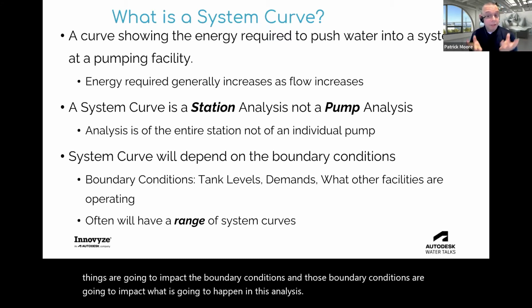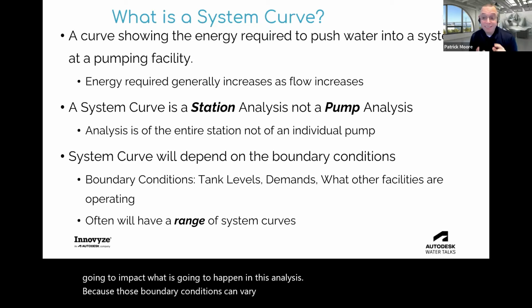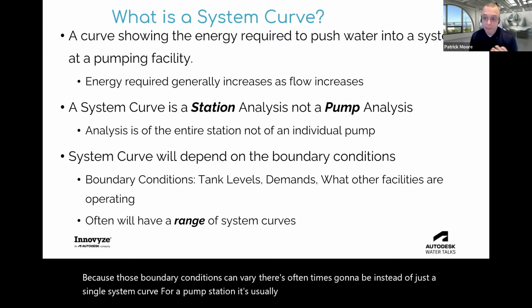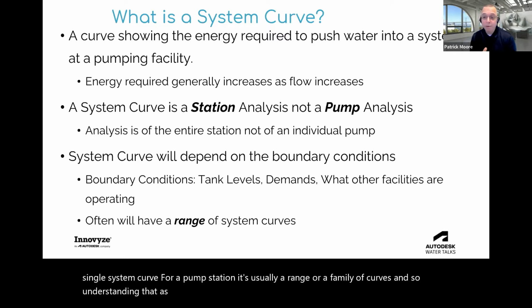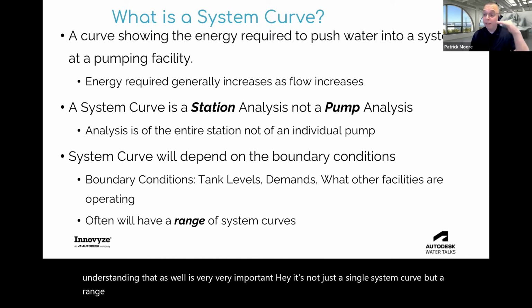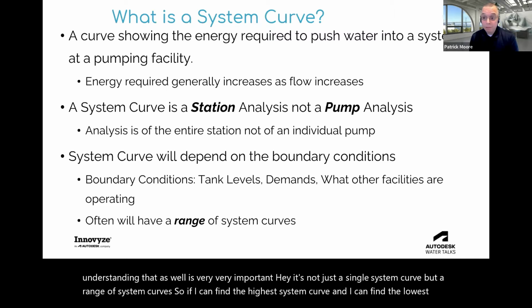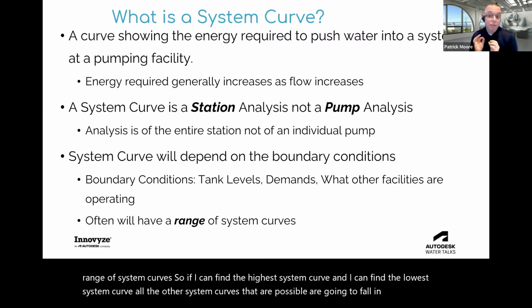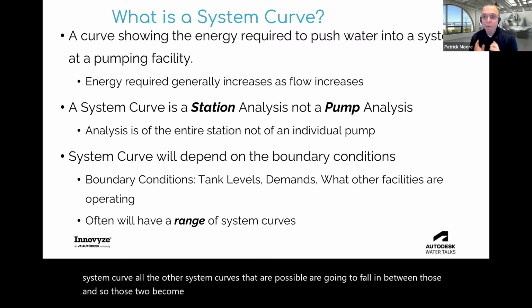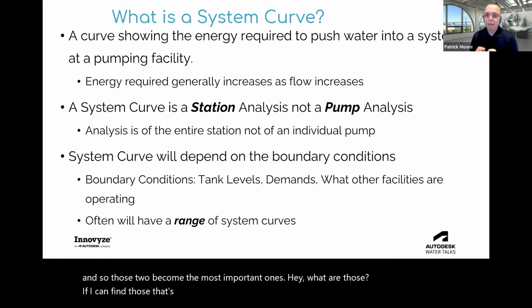Because those boundary conditions can vary, there's oftentimes going to be, instead of just a single system curve for a pump station, usually a range or a family of curves. And so understanding that as well is very, very important. It's not just a single system curve, but a range of system curves. So if I can find the highest system curve and I can find the lowest system curve, all the other system curves that are possible are going to fall in between those. And so those two become the most important ones. If I can find those, that's the most important ones that I need to analyze, because all the other ones are going to fall in between.